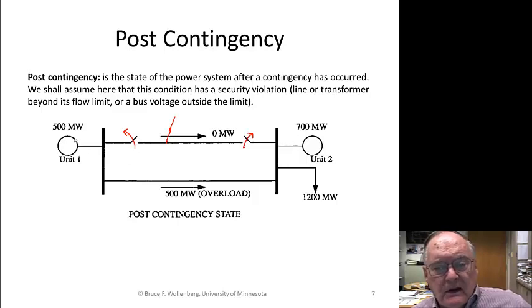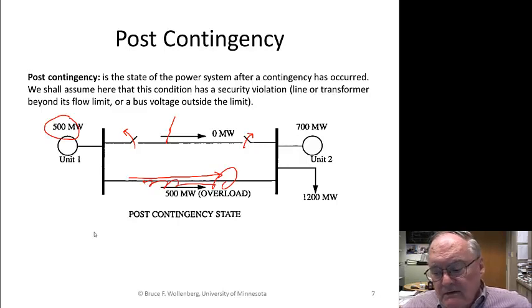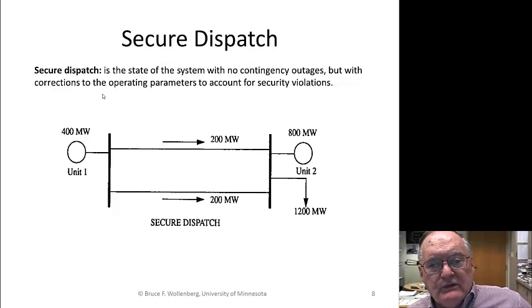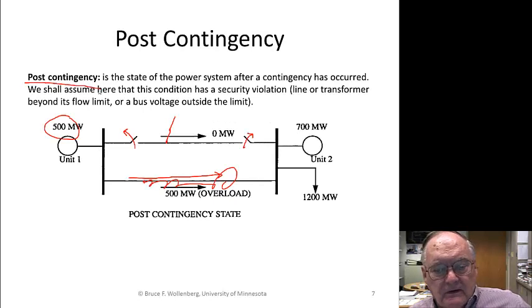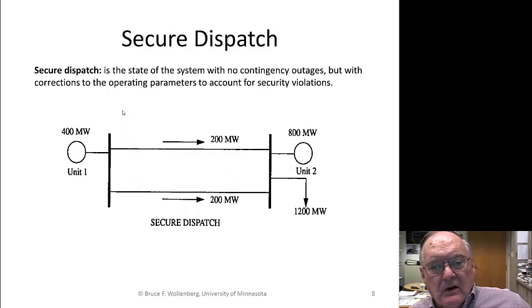As soon as I opened it, this 500 is now coming in here, and this line here is going to heat up, literally heat up, and start to sag and to fail. So the post-contingency condition of that first outage says we've got an overload. Now, the secure dispatch: if the operator, this gets detected by a what-if test, says your post-contingency state has an overload, then we run a secure dispatch, and what it would do is say, well, I can load this up to a maximum of 400, and then I have to pick up the other 100 here. So I had to run this one down, and I had to run this one up. This one from 500 to 400, and this one 700 to 800.